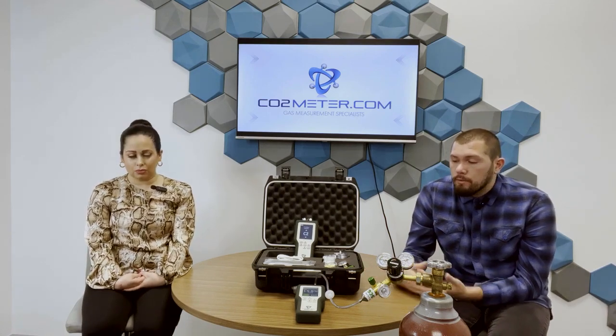Any gas detection or measuring device requires a little bit of maintenance. The big thing we think about is calibration. The device comes to customers factory calibrated with a certificate, guaranteeing that calibration for a year. So we suggest annual calibration. Because the device features 4 sensors internally, the calibration can be a little tricky, so we suggest sending it back to CO2Meter. We'll do that calibration and get it back to you in a timely manner, annually.